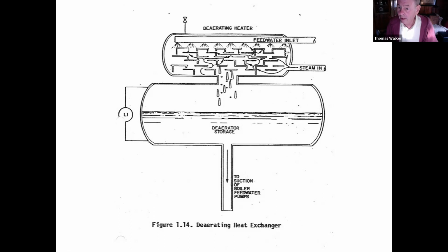Because I'm heating up the water, I would also like to know its temperature. So I need a thermometer of some type or a temperature indicator. And then finally, because I'm adding steam to it, I need a pressure gauge. So I need to know the steam pressure, the temperature, and the level. And that's it.